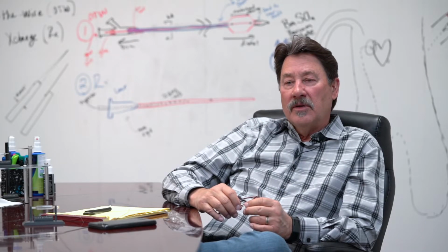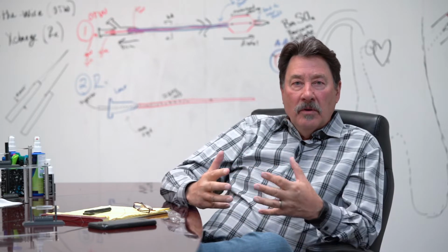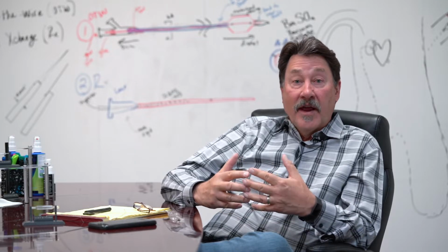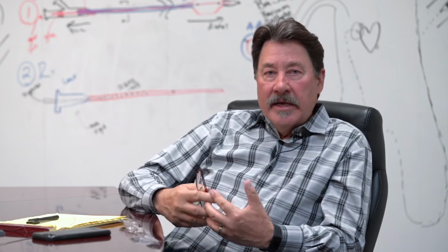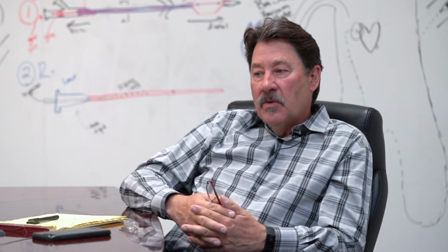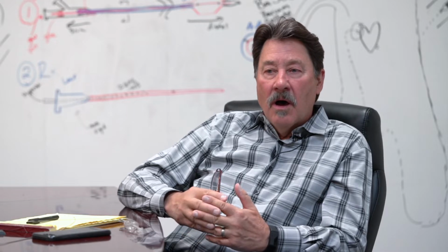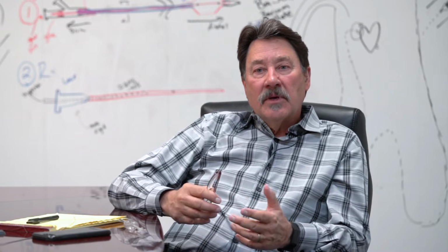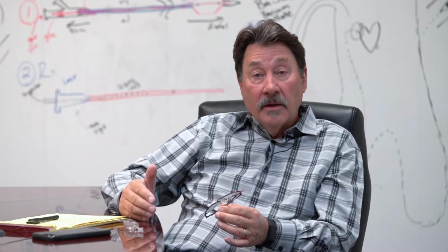When you talk about design inputs, these are going to ultimately go into what becomes the design history file. It ultimately becomes what you manufacture to. When we look at a product concept, a person that's got an idea, they want to have it developed, one of the first things that we want to focus on is trying to work on what are the actual design inputs. And the design inputs are a list of minimum requirements to create a product that's going to function.